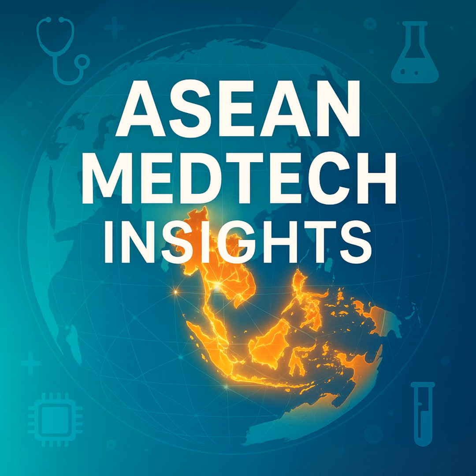A common misconception is that entering the ASEAN market requires conducting new, local clinical trials for every device. This is often not the case. The guidance allows manufacturers to leverage existing clinical data from various sources. This can include data from clinical investigations of your device, scientific literature on equivalent devices, and post-market surveillance data from other markets like Europe or the United States.